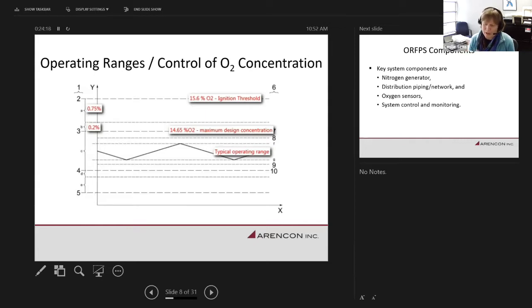Then over time, you'll see the oxygen level starts to rise again through losses, through infiltration in the building, opening and closing doors, and just the tendency of the space to mix and return to natural ambient conditions. So you hit a high point, and that's a demand point, where the system calls for more nitrogen. You inject more nitrogen, and you'll cycle this way over the life of the building, with the nitrogen cycling up and down within a bandwidth that is below the design concentration level and above what we'd call an environment with too little oxygen, where we either don't want people entering the space, or it's just not efficient. We'd just be pumping nitrogen in with no efficiency.